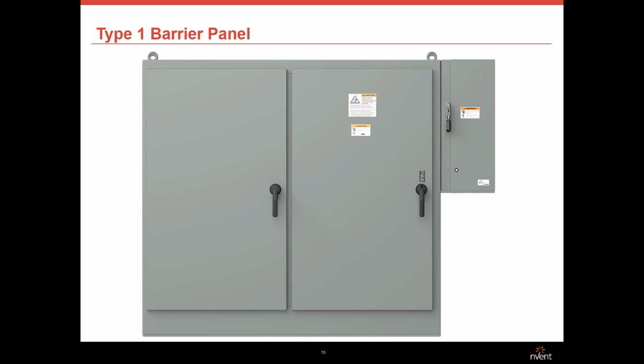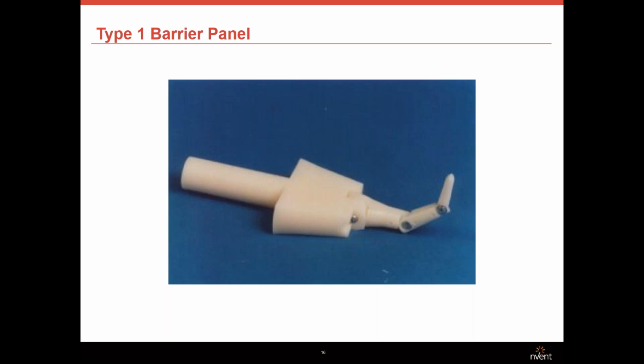So one of the advantages I talked about was having a Type 1 barrier panel. With your barrier panel properly installed in the control enclosure, the enclosure can be separated into multiple Type 1 enclosures if you are using a Type 1 rated barrier panel. If the barrier panel being utilized is not a UL Type 1 rated panel, the installation will not be separated into Type 1 panels when the doors are open. So you need to have a Type 1 rated panel to get the benefits that I'm about to talk about. To be a Type 1 rated panel, the panel would need to pass the probe test when installed. Illustrated is the articulated UL probe. To oversimplify it, if the probe can reach any surfaces that electrical components will be mounted to, it fails the test.